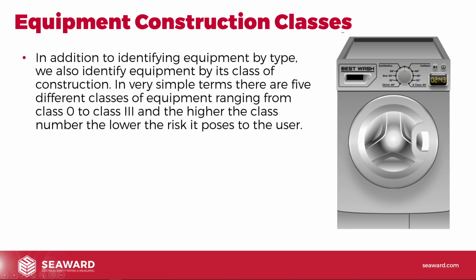So now we're going to take a look at equipment construction classes. You may well have heard of people talking about Class 1 and Class 2 equipment. Now we're going to take a deep dive into it and give you the background on what that actually means. So in addition to identifying equipment by type, we also identify equipment by its class of construction. In very simple terms, there are 5 different classes of equipment, ranging from Class 0 to Class 3. So basically, the higher the class number, the lower the risk it poses to the user.